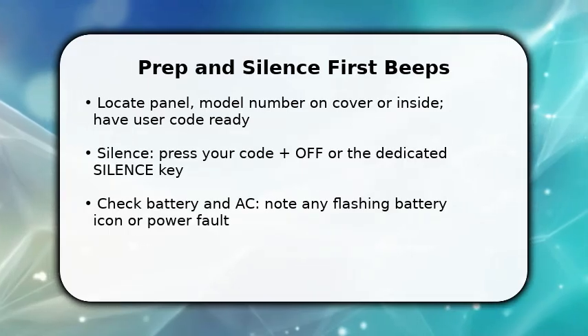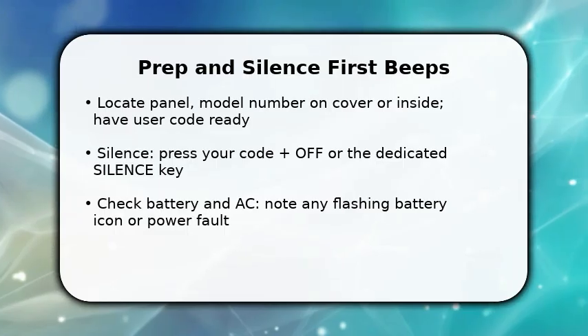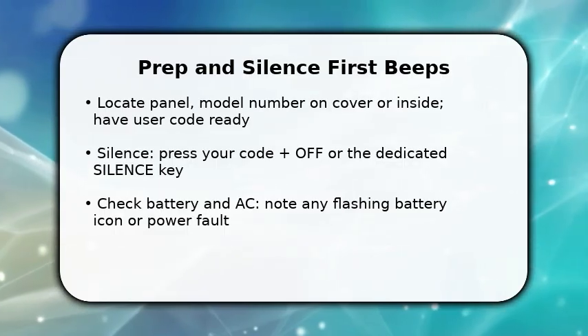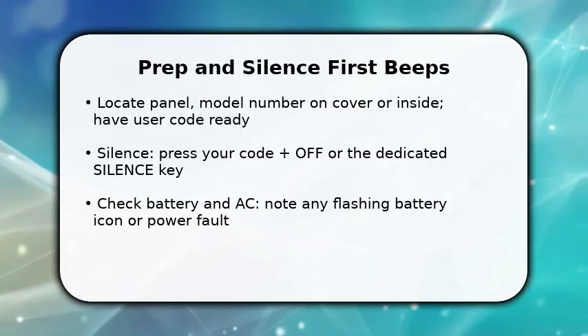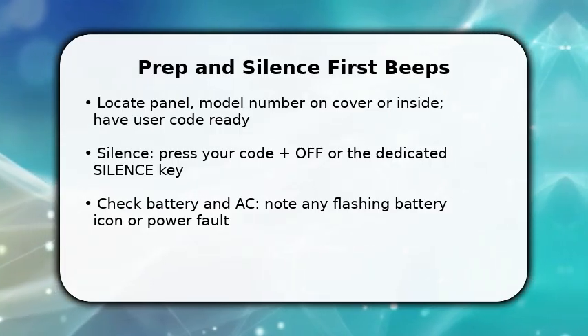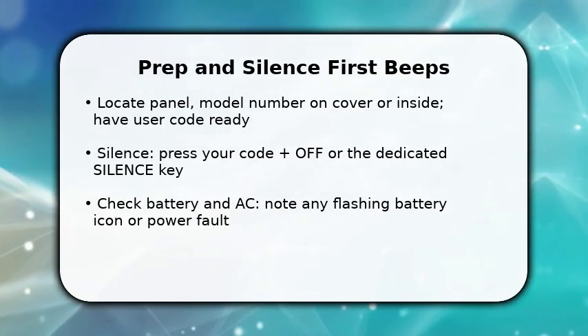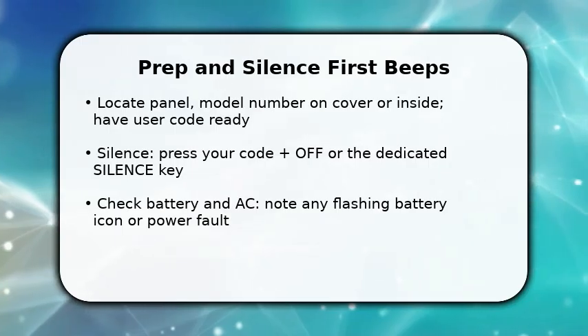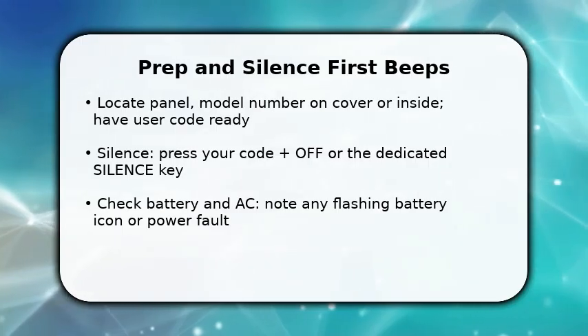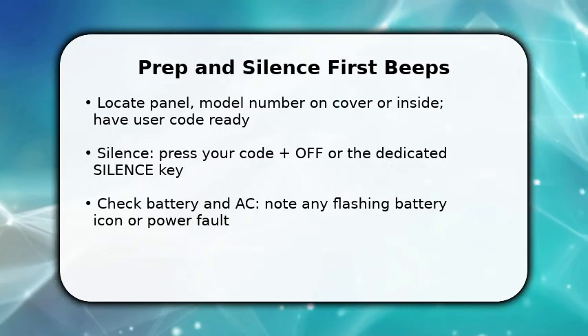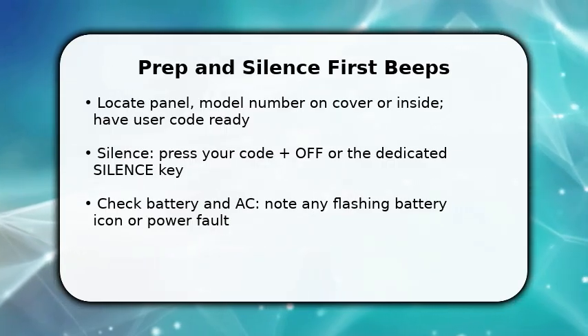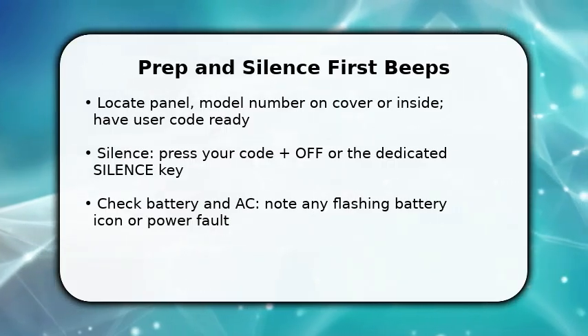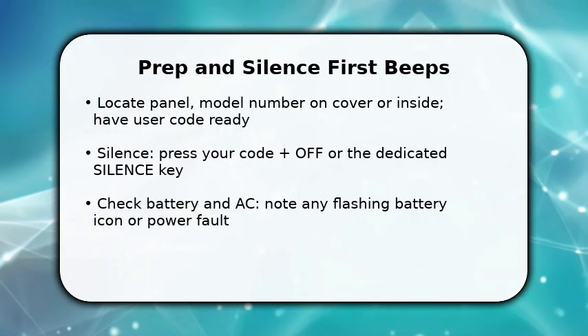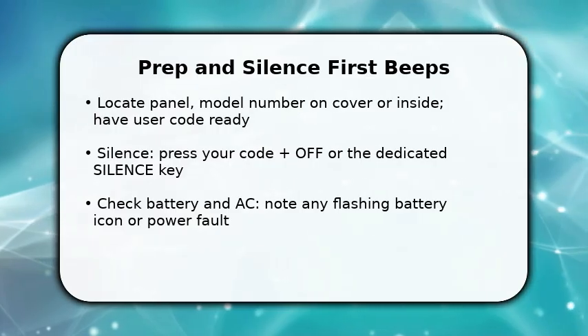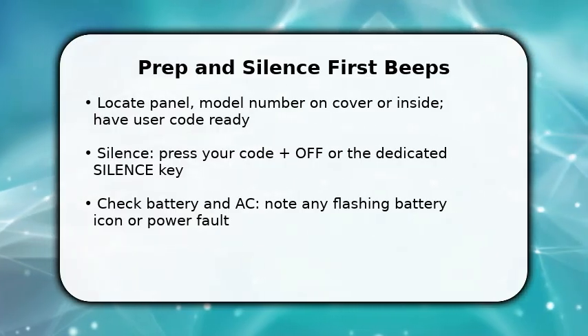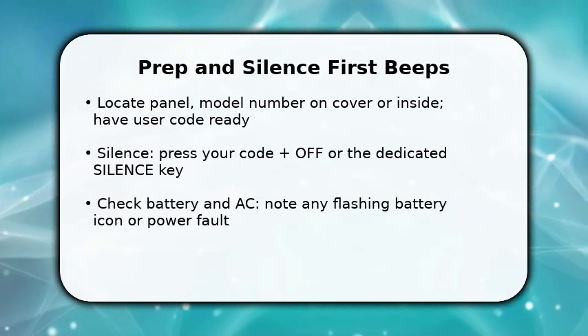You start by stopping the immediate noise. Open the panel, confirm the Honeywell model, and have your user code at hand. Enter your code and press OFF or the silence key to mute beeps. This addresses transient alarms. Once done, inspect the display for battery or AC fault icons. Those cause repetitive chirps. Make sure the system is not reporting an active alarm condition before proceeding. That prevents resetting the wrong issue and keeps you from missing a real alert.